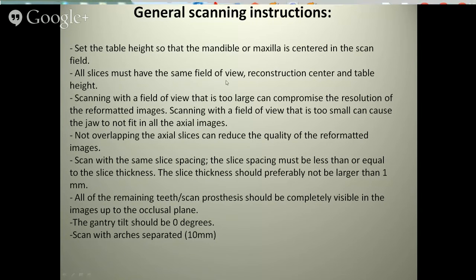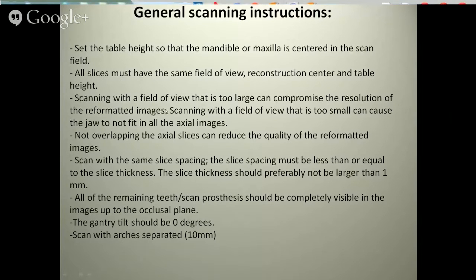All slices must have the same field of view, reconstruction center, and table height. Scanning with a field of view that's too large can cause a compromise in the resolution of the formatted images - basically, we've seen scans that look distorted because of this. Field of view can affect that.